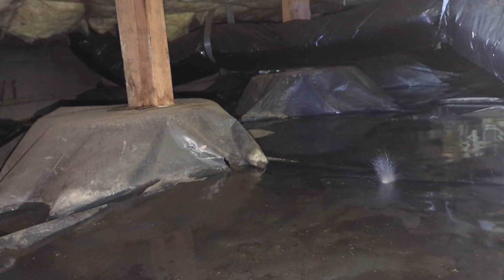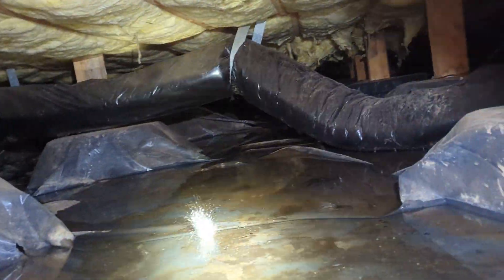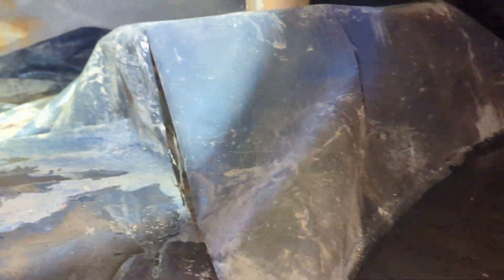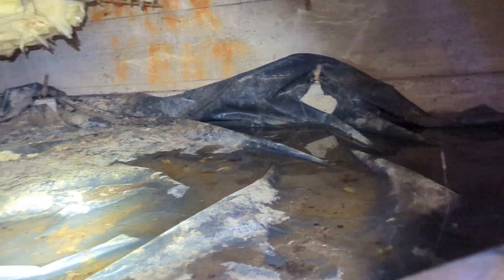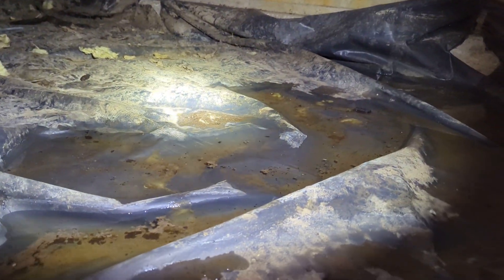Got lots of areas of disconnected ductwork, ductwork in direct contact with water, so we'd recommend an evaluation and probably repair or replacement, certainly cleaning — if nothing else, re-elevation and cleaning of those areas — because having water inside your ductwork is bad.